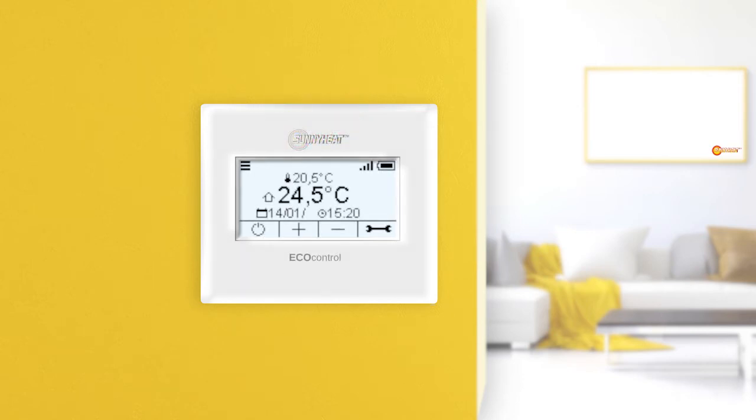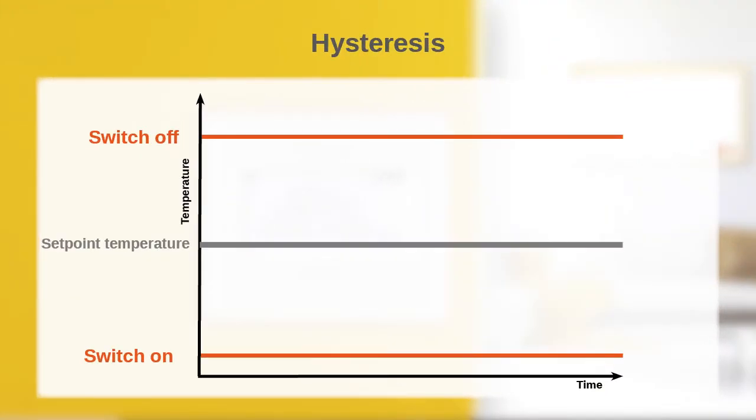Most thermostats work with a hysteresis to control the room temperature. Let's assume that the hysteresis is half a degree Celsius. This means that the heating heats until the room temperature is half a degree Celsius above the setpoint temperature.